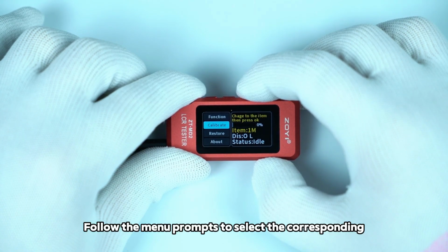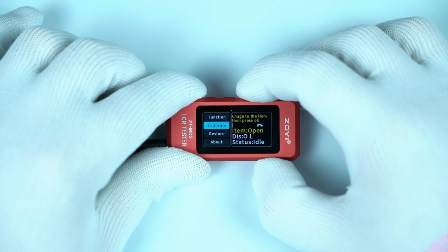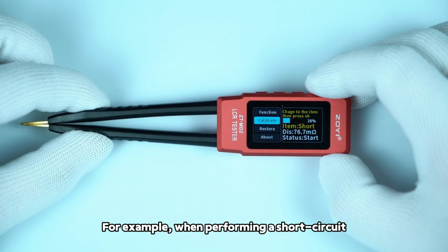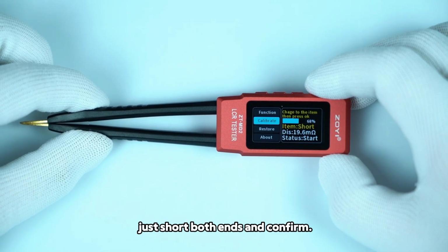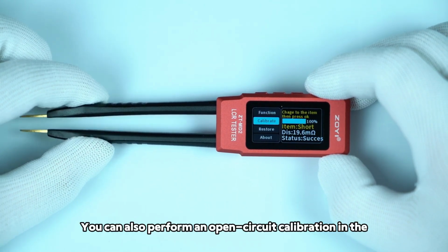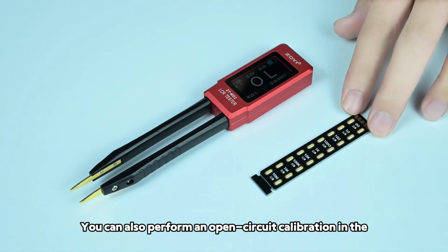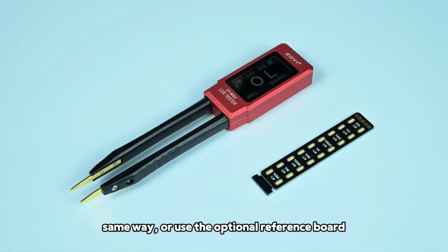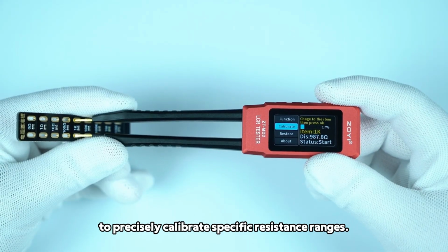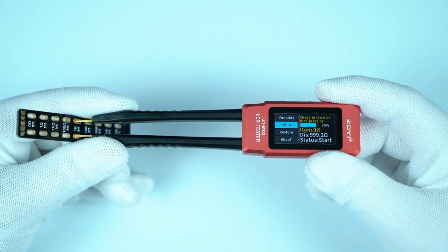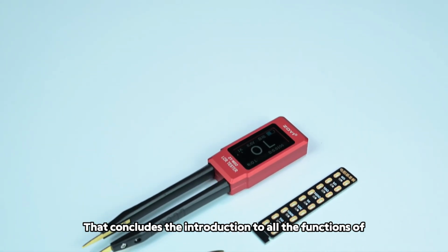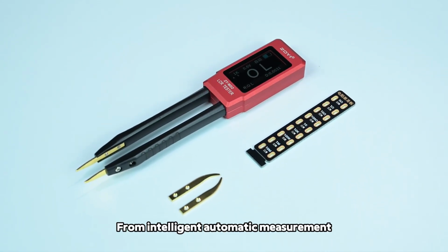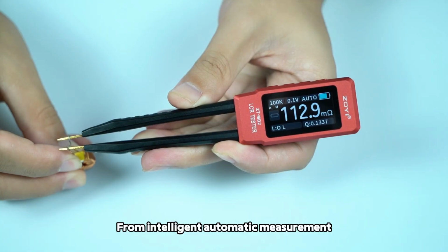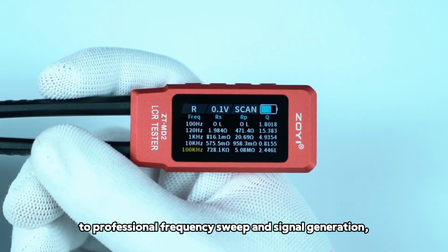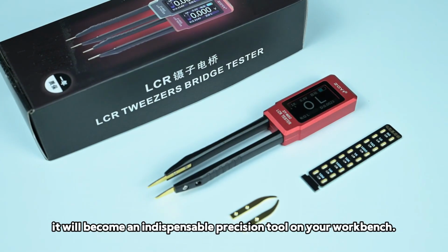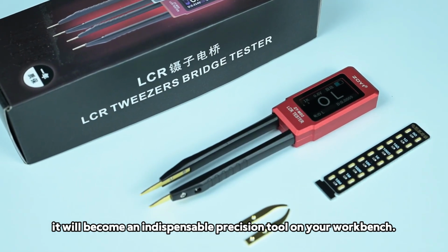Follow the menu prompts to select the corresponding calibration item. For example, when performing a short circuit calibration, just short both ends and confirm. You can also perform an open circuit calibration in the same way, or use the optional reference board to precisely calibrate specific resistance ranges. That concludes the introduction to all the functions of the MD2. From intelligent automatic measurement to professional frequency sweep and signal generation, it will become an indispensable precision tool on your workbench.